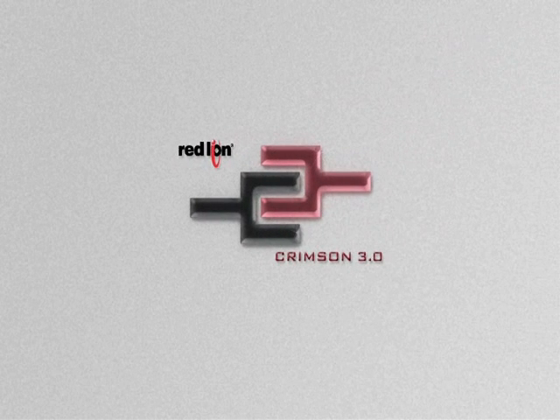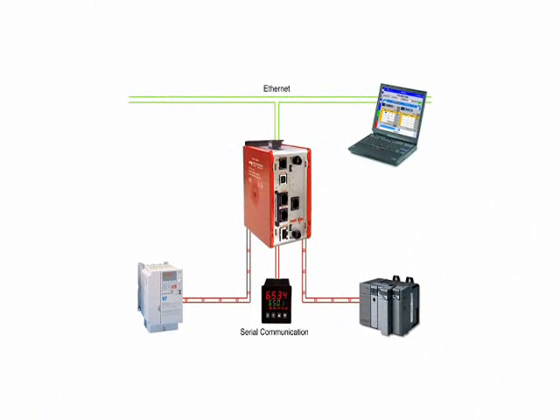In this video, I will show you how to do protocol conversion using Red Lion's Crimson 3 software and our Data Station Plus. In this example, we'll say we have an Allen Bradley PLC that only has an RS-232 port, and we want to expose that information as Modbus over Ethernet to a SCADA system running Modbus TCP/IP. For our purpose here, we'll assume the SCADA is the master, so we want our Ethernet port on the data station to be a Modbus slave.